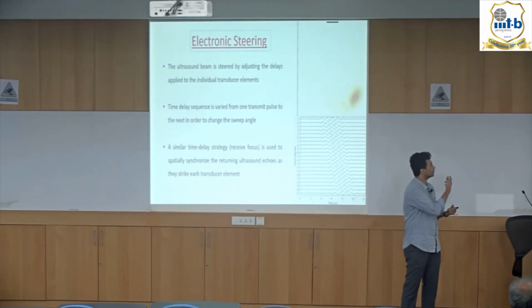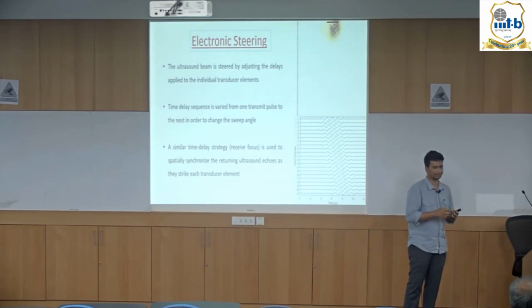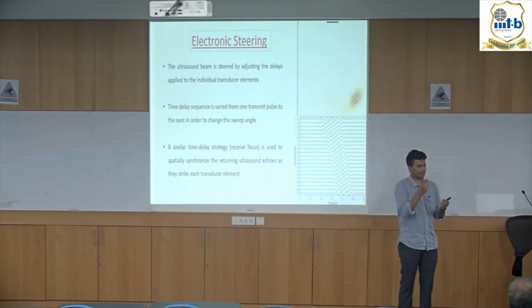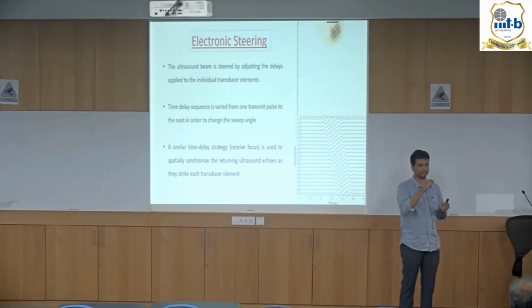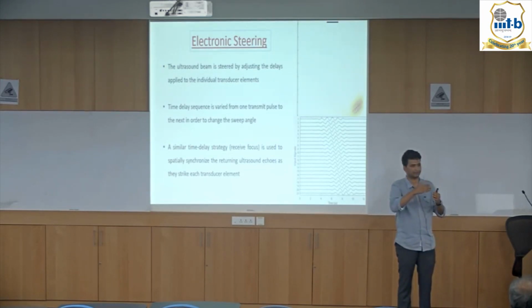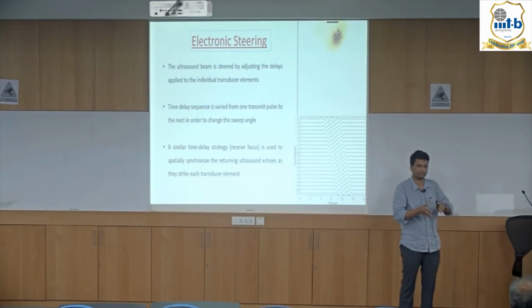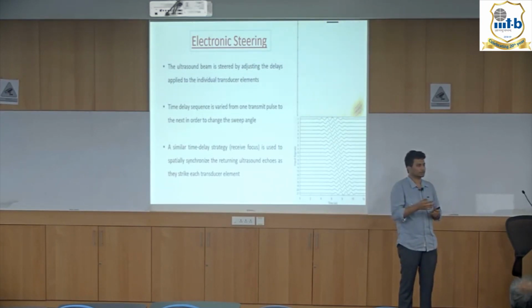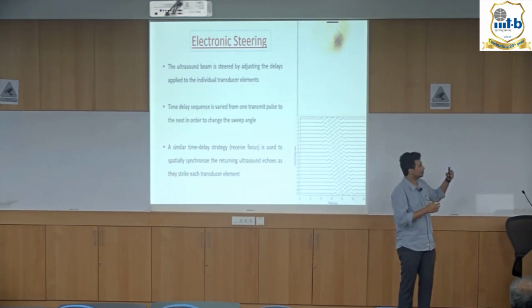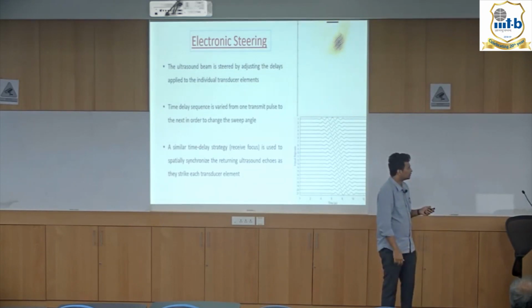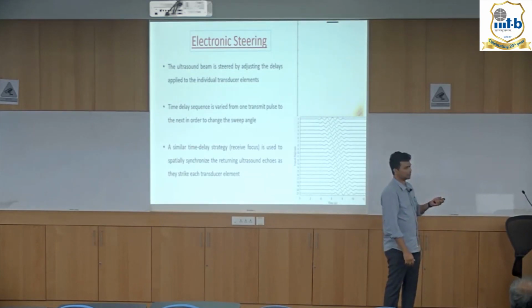So they came up with electronic steering. What happens here is the electric signals given to the transducer are not synchronized. Each transducer is fired at a different point of time. Because of that, constructive and destructive interference occurs, and the resultant beam moves at an angle. So the beam is directed electronically, not manually. This is what is being done nowadays.